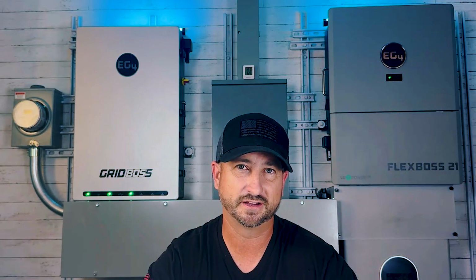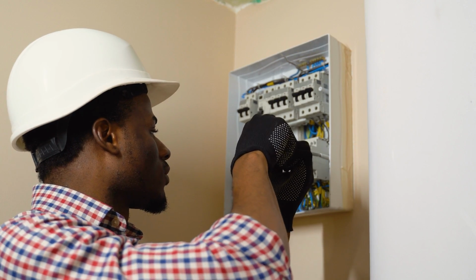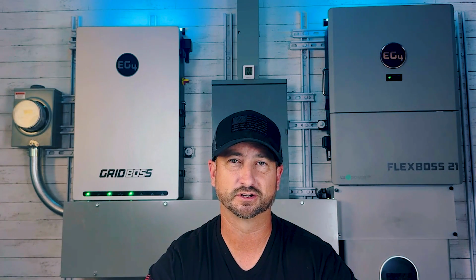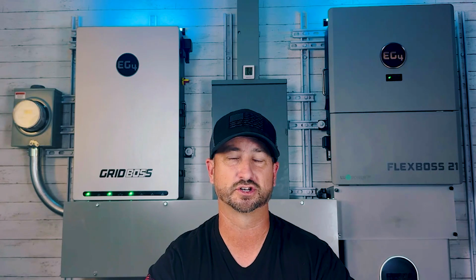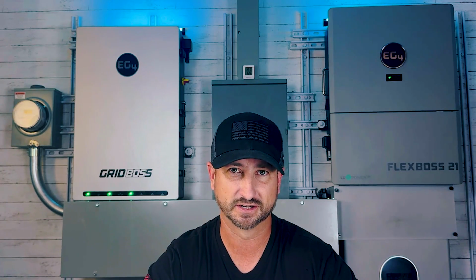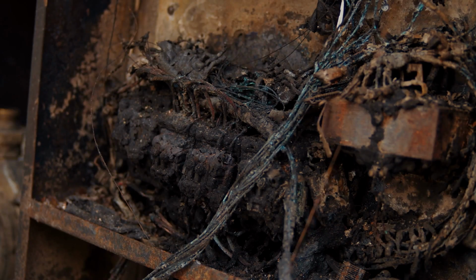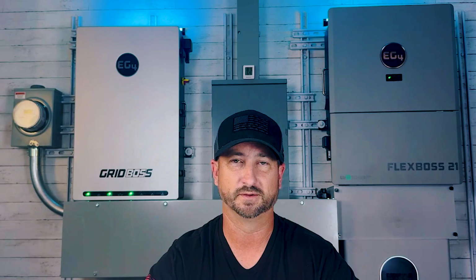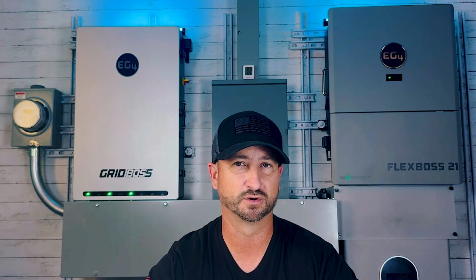Another common mistake is loose connections at the terminals. Whenever you're making connections, quadruple check that they're torqued to the right specs. If wires start to shake loose — remember, electricity, especially AC, oscillates back and forth — a loose connection will keep wiggling looser over time. Those connections will heat up dramatically and could even cause a fire. Make sure all your wire connections are tight; yank on them hard to make sure they're firm. The best way to ensure that is to use the proper tools for the job.